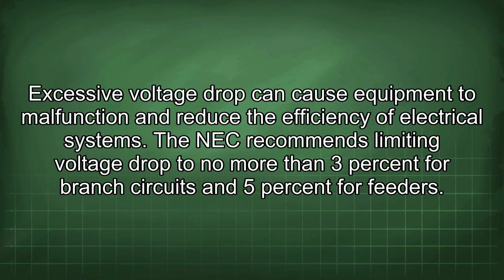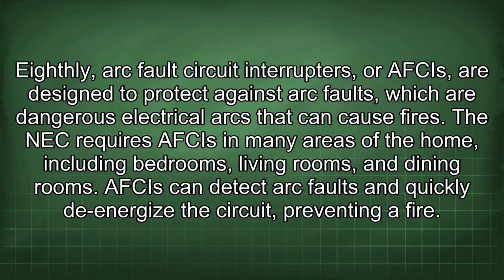The NEC recommends limiting voltage drop to no more than 3% for branch circuits and 5% for feeders. Eighthly, arc fault circuit interrupters, or AFCIs, are designed to protect against arc faults, which are dangerous electrical arcs that can cause fires. The NEC requires AFCIs in many areas of the home, including bedrooms, living rooms, and dining rooms. AFCIs can detect arc faults and quickly de-energize the circuit, preventing a fire.